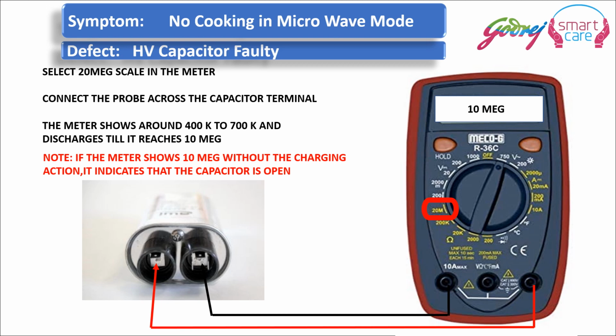It should charge initially. The charging action is shown when it is initially showing a resistance of 400 kilo ohms to 700 kilo ohms. But if it directly shows 10 mega ohms, it indicates that the capacitor is open. For charging and discharging of the capacitor, initially the capacitor shows 400 kilo ohms to 700 kilo ohms, and then in a few seconds the reading across the capacitor shows 10 mega ohms. If not, then it is faulty.